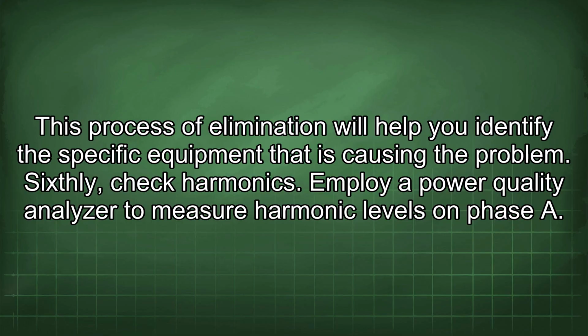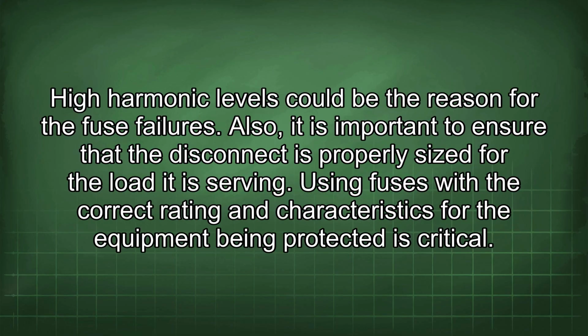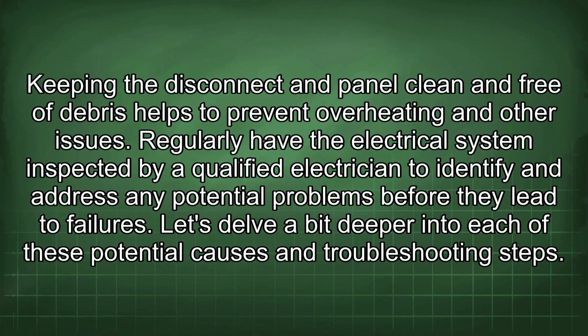Sixthly, check harmonics. Employ a power quality analyzer to measure harmonic levels on phase A. High harmonic levels could be the reason for the fuse failures. Also, it is important to ensure that the disconnect is properly sized for the load it is serving. Using fuses with the correct rating and characteristics for the equipment being protected is critical. Keeping the disconnect panel clean and free of debris helps to prevent overheating and other issues. Regularly have the electrical system inspected by a qualified electrician to identify and address any potential problems before they lead to failures. Let's delve a bit deeper into each of these potential causes and troubleshooting steps.